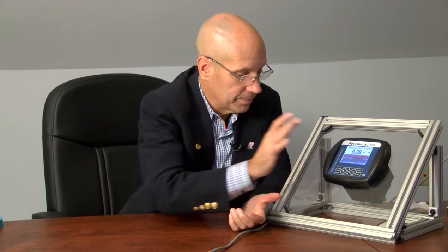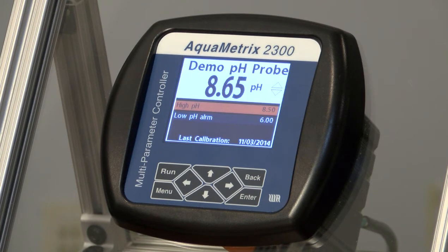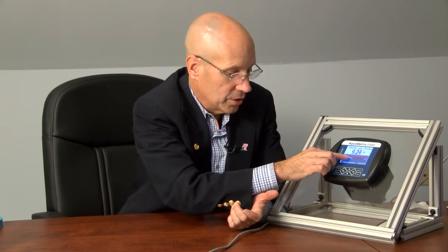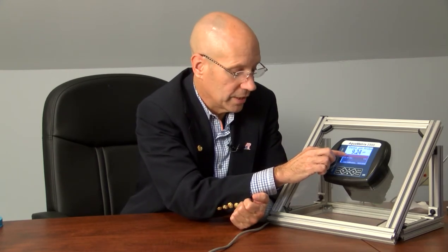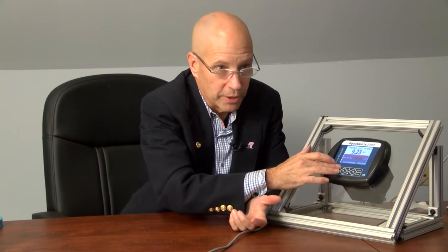As informative as this run screen is, it's limited. To check in on any one probe, just press the right arrow key. If there's more than one probe, I would have to press the right arrow key more than once. This is what we call the detail screen. If an alarm has been triggered, you will see the name of the alarm and the trigger value for the alarm surrounded by a red rectangle. If the alarm has not been triggered, then 2 values will be surrounded by a green rectangle. The same is true for an activated relay, except that the surrounding rectangle, like it is now, is yellow. To get back to the run screen, just hit Run.